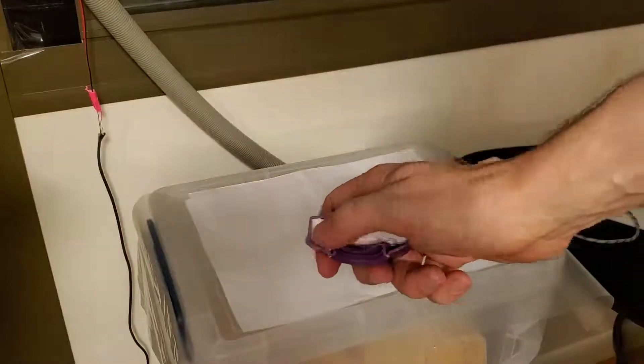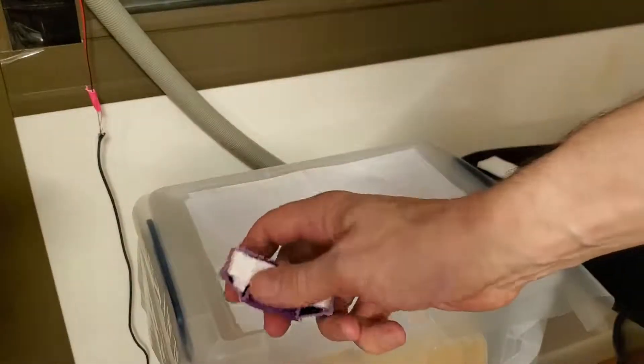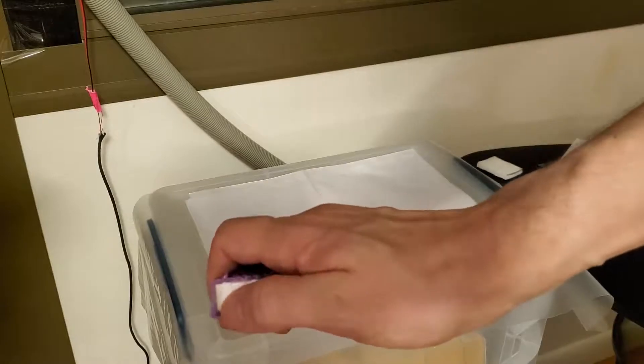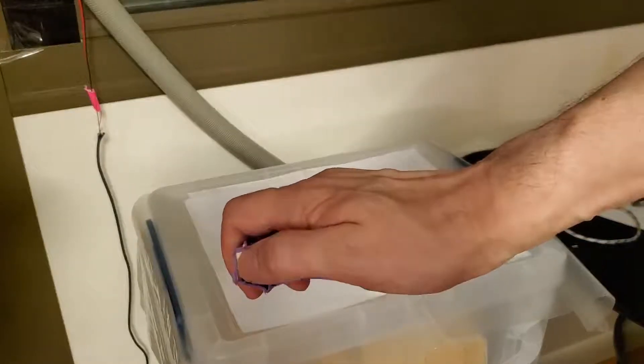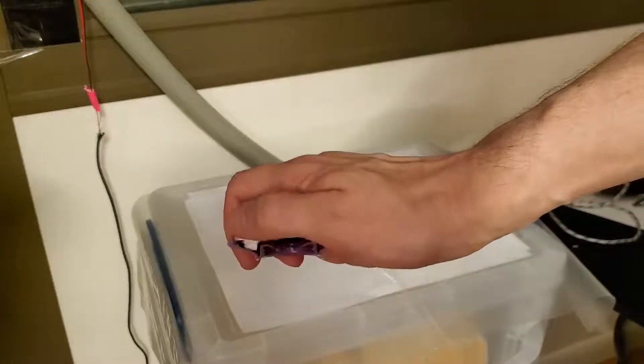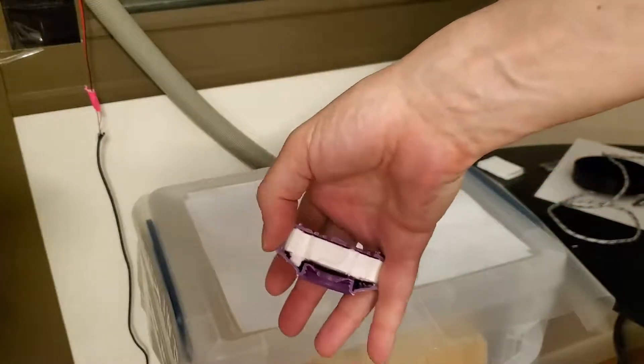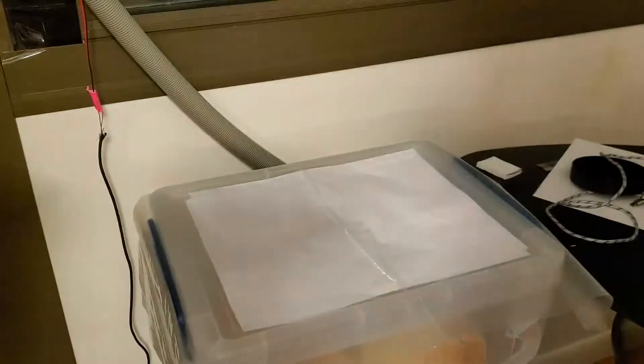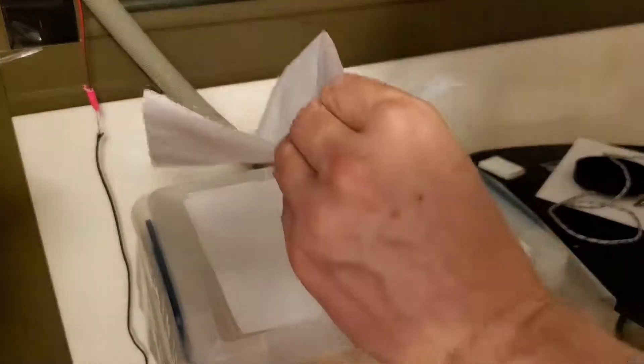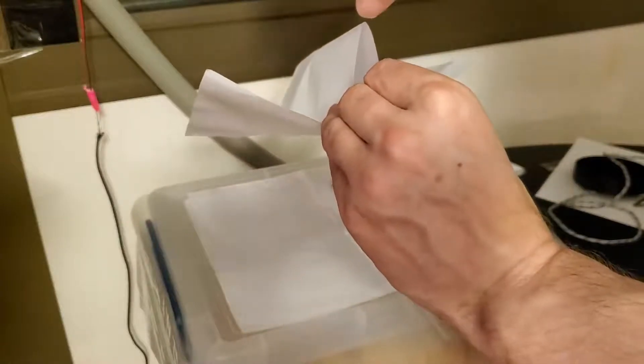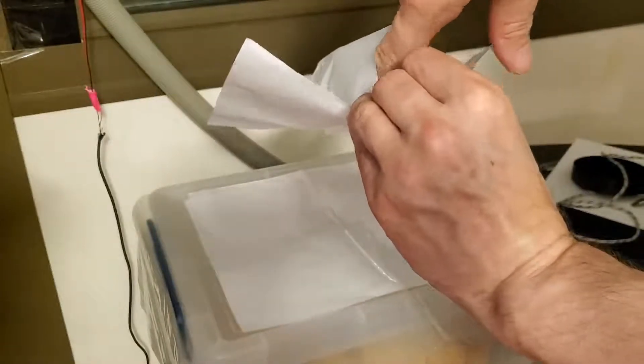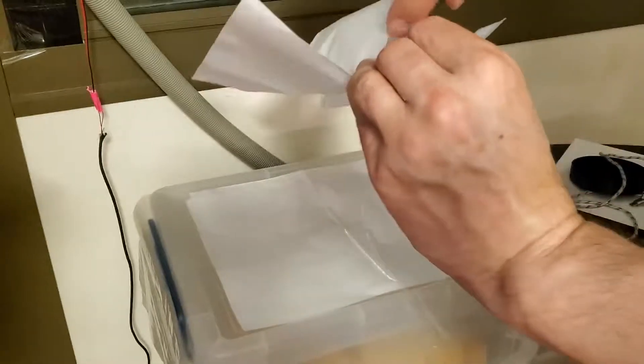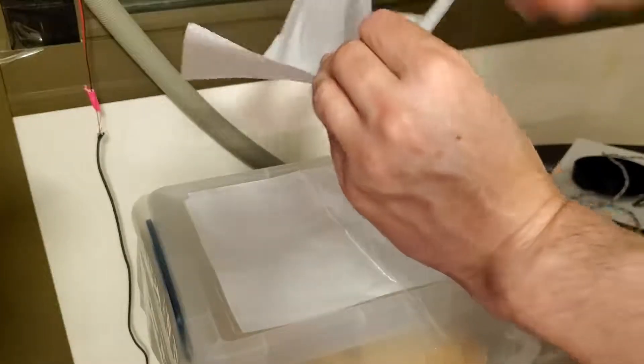If you look at a well-made protective filter, there will be a heavy coating of sealant between the housing—the thing that holds the filter—and the edges of the filter. What this is for is so that air doesn't get in through one of the folded edges and pass from one side to the other without being filtered.